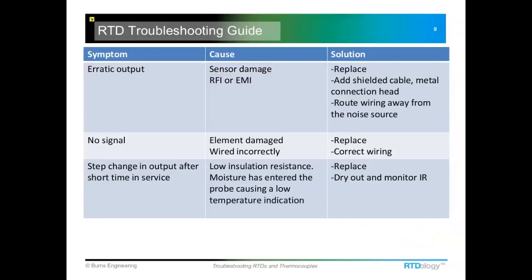One of the most common issues people run across is an erratic output — the temperature jumps up and down. Sometimes it might even read okay, and then the temperature will go up. That's typically an indication that the sensing element has been damaged. If you imagine that little coil of platinum wire vibrating past what it can survive, the wire starts to fracture just a little bit, changing the resistance and causing the indicated temperature to jump around. As that fracture vibrates, the resistance can change quite a bit and eventually could go open circuit.